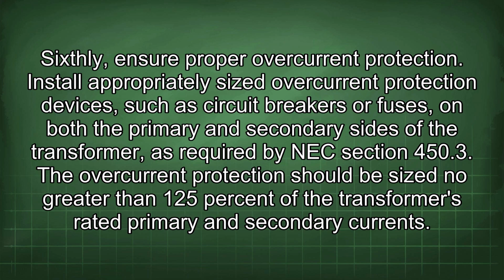Sixthly, ensure proper overcurrent protection. Install appropriately sized overcurrent protection devices, such as circuit breakers or fuses, on both the primary and secondary sides of the transformer, as required by NEC Section 450.3. The overcurrent protection should be sized no greater than 125% of the transformer's rated primary and secondary current.